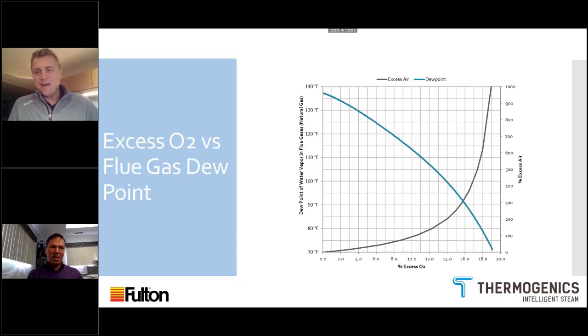And if there's no condensate coming out of it, you're at that 85–86% efficiency range. And those places were designed to be 90%. So there is about the telltale sign. When you see that it's always dry, that means it's not condensing. Yeah, and that likely has to do with incomplete combustion or inaccurate combustion setup. This is really, really common as hospitals or anybody are implementing condensing technology, or they're going to higher turn down burners on their existing boilers. I thought this was relevant to bring up because we get calls about it every day. Absolutely, that's 100% useful.